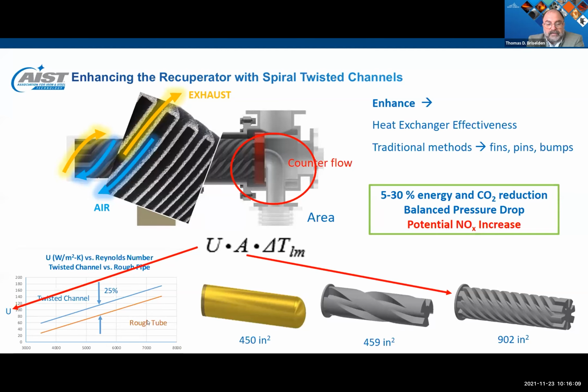Increasing the surface area with the assistance of additive manufacturing allows for a significant change in surface area as compared to fins and bumps. A typical tube recuperator will have a surface area of 450 square inches. A shallow twist 3-fin design can match this surface area. However, when increasing both the number of twisted channels and twist rates, a surface area of 2 times is achieved. The corresponding improvement in heat transfer coefficient allows overall radiant tube efficiencies to approach 85%. Thus, 5 to 30% energy and carbon reductions can be realized. The combined reduction of flow rate and improved heat transfer coefficient and counterflow design allow pressure drops to be minimized in the overall system.